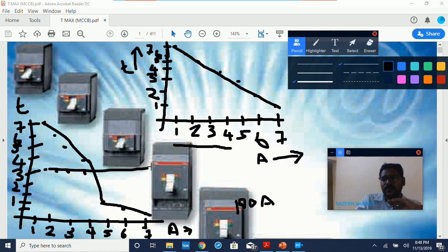Between voltage and current, all electromagnetic devices, like a bike speedometer or electromagnetic disc operated devices, all physical components, can perform only this one, inverse. You can note it now. All other components, electronic components, have all 3 characteristics in the trip unit. They have to select it; in an electronic unit, it will have a display. If this relay wants to operate in inverse, they will select inverse mode. On some other day, if they want extreme inverse, they will select this mode.